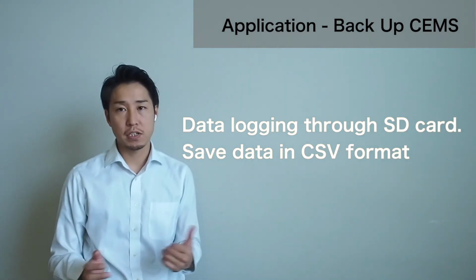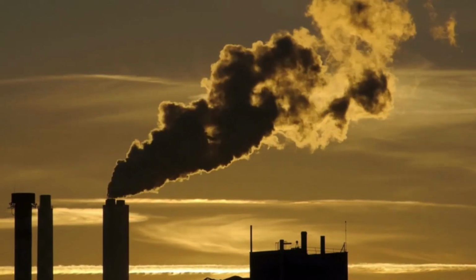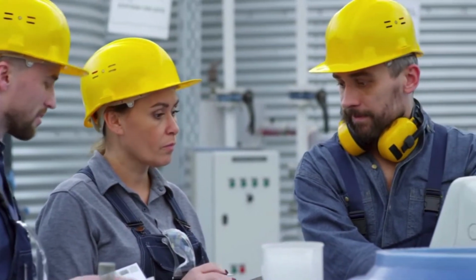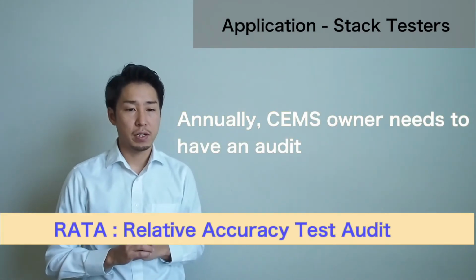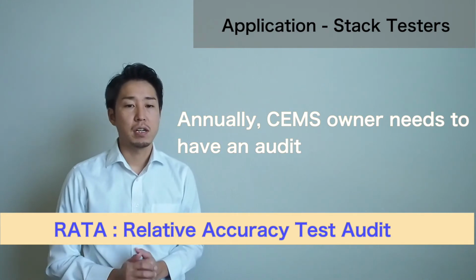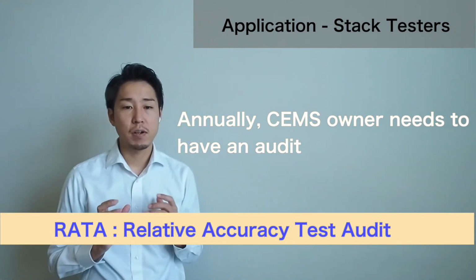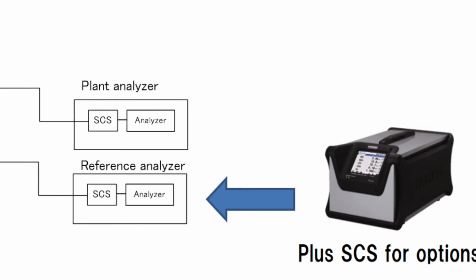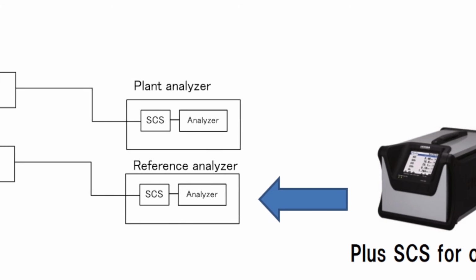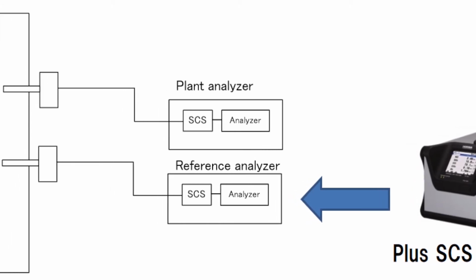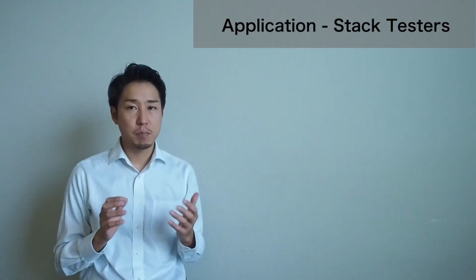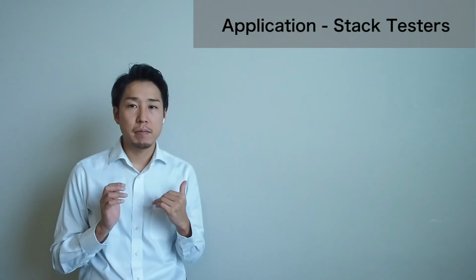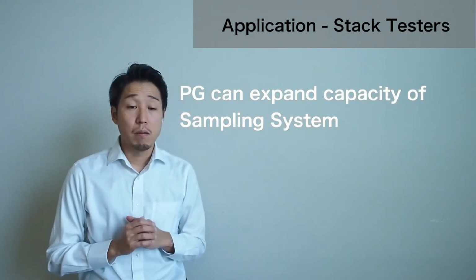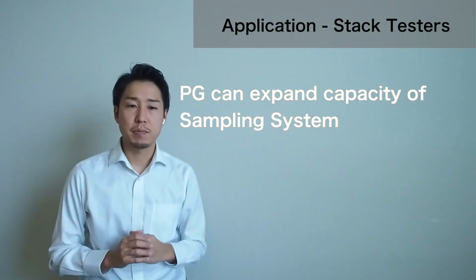So let's talk about the application for the stack testers. Basically, a stack tester comes to the plant to validate that their CEMS is working properly. The CEMS owner needs a report that shows the CEMS passed, and it's called RATA, Relative Accuracy Test Audit. For this validation, the stack tester needs to provide the same configuration as the CEMS to compare. So you will need a probe, heated bundle tubing, and an external sample system. Since PG is very compact and has the sample system inside, its capacity is limited. We have an external sampling system to expand that capacity.